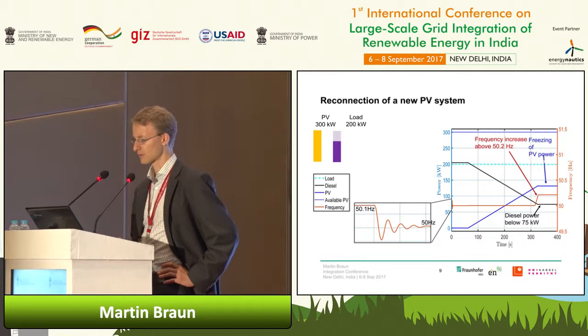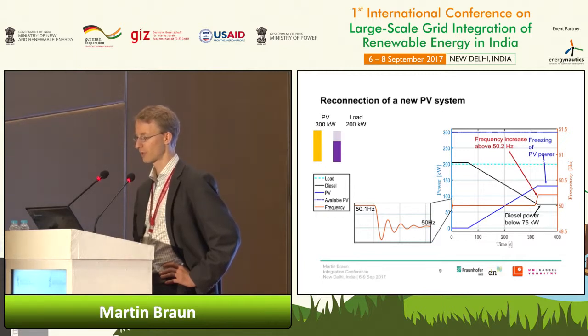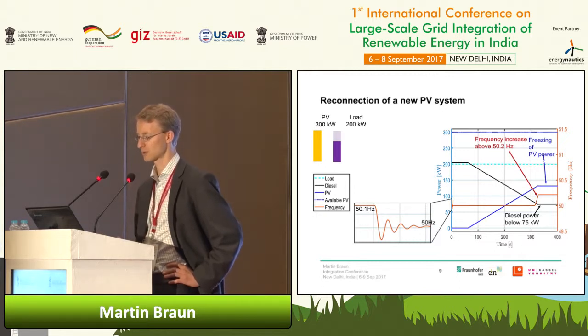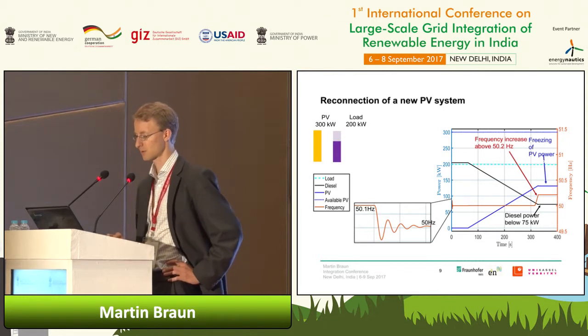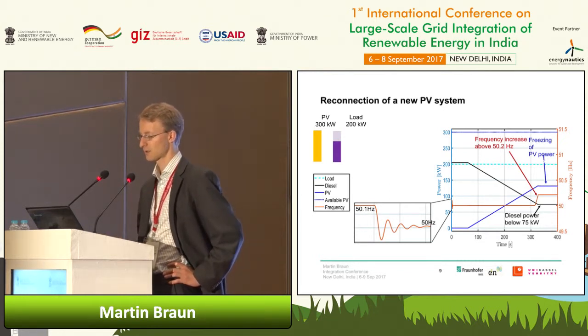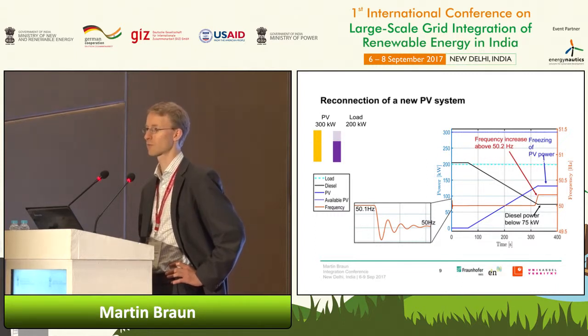And so it's increasing until reaching a certain value, and if a certain power is reached, then the frequency goes up because the active power of the diesel genset is going to an underload constellation, and then the PV power is actually frozen at a lower value. So see, it's not 300 kilowatt, but it's around 130 kilowatt, according to the frequency signal.